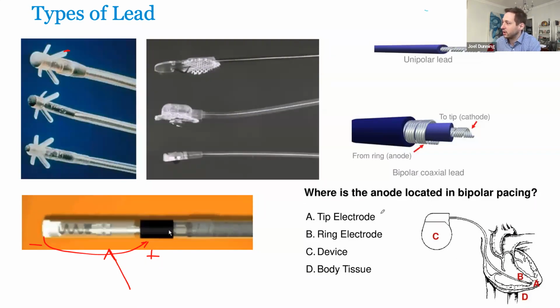So where is the anode located in bipolar pacing? You have your cathode, your negative here, and then your anode will be at your ring electrode, or if it's an integrated lead like you have with Boston, it could be your conductor coil. So it's just going to be a little more proximal, but we're not going to the can. If you're going unipolar, then it would be the tip to the can being the positive. And why does the positive and negative matter? It's just how you complete the electrical circuit. The electrons are going to flow from negative to positive.